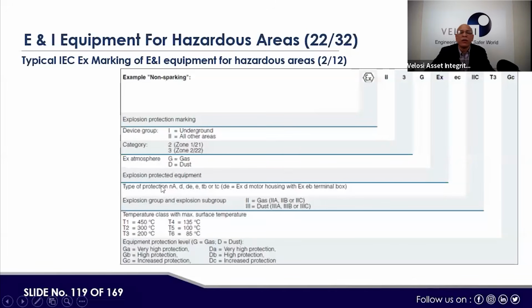Then for explosion protected equipment, we have the type of protection. Then the explosion group and subgroup: 2 for gas and 3 for dust. For gas we have 2A, 2B and 2C, and for dust 3A, 3B, 3C. Then temperature class, maximum T, as we already went through: T6 is 85 degrees C, T1 is 450 degrees C, depending on what temperature can potentially be borne in that area. Then equipment protection level, G or D for dust. This is the first slide we remember. So for each equipment we need to fill in these tables: nine things are required to be answered for each equipment, right? So don't worry, it is step by step.